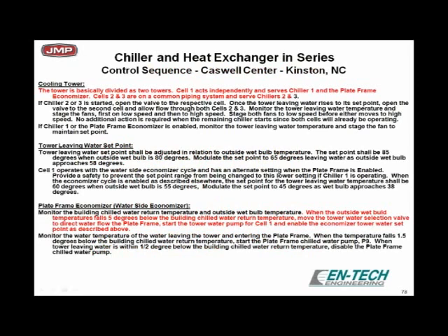Here's a typical control sequence that a friend of ours is using. I think the bottom line of all this is he's using a dedicated cell for the waterside economizer. He's turning on that waterside economizer dedicated cell anytime that the wet bulb temperature is 5 degrees below the chill water return temperature. That's the magic. Anytime the outdoor air wet bulb temperature is 5 degrees below the chill water return temperature, you can save a bunch of money by starting to integrate the waterside economizers in with the chillers.